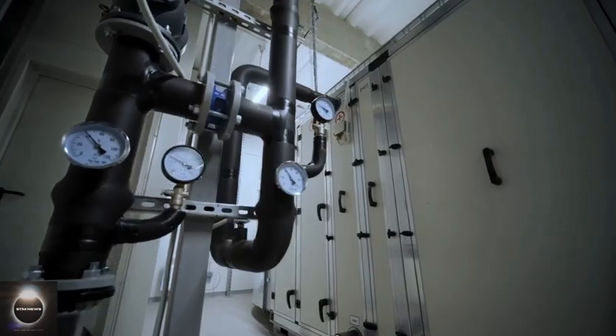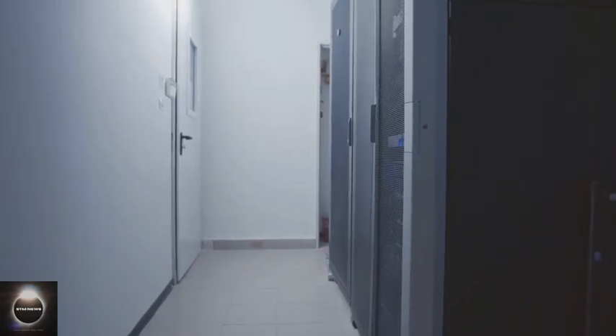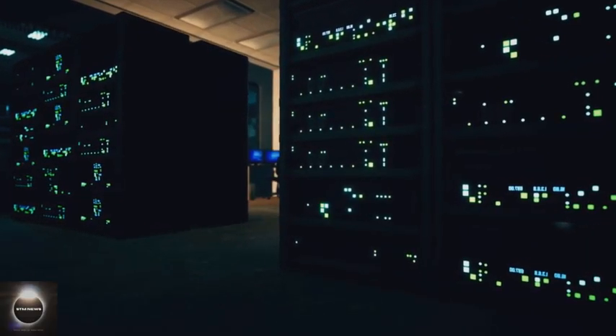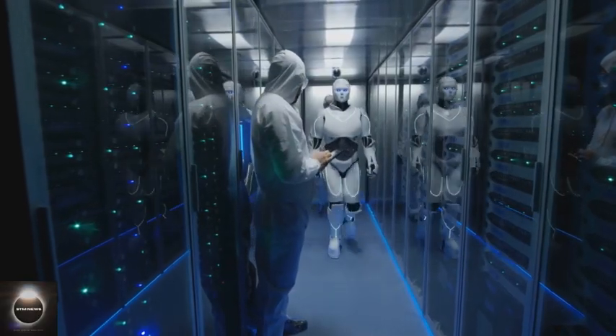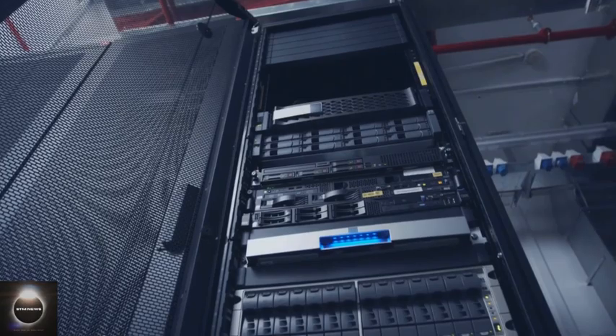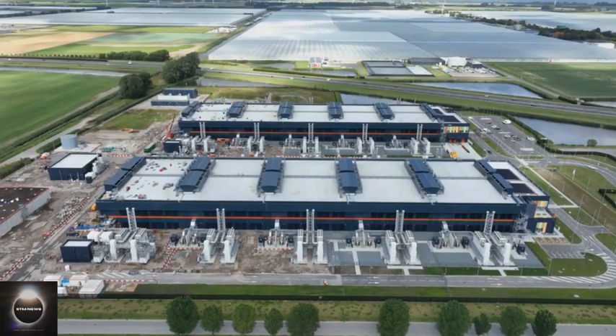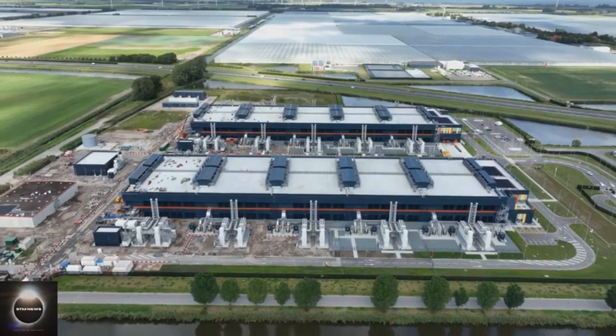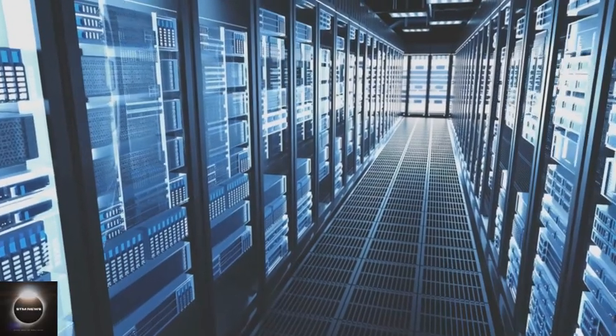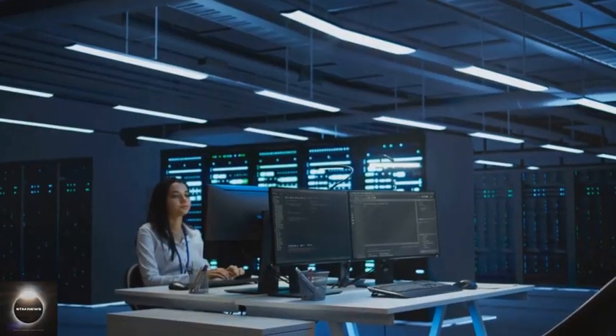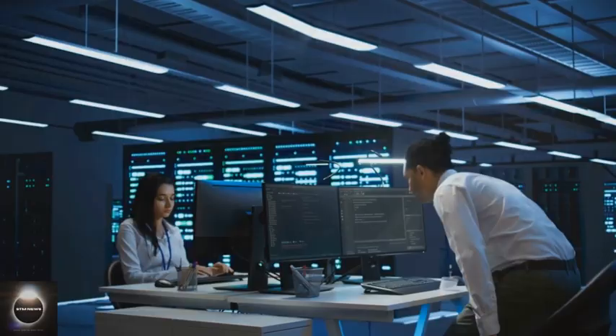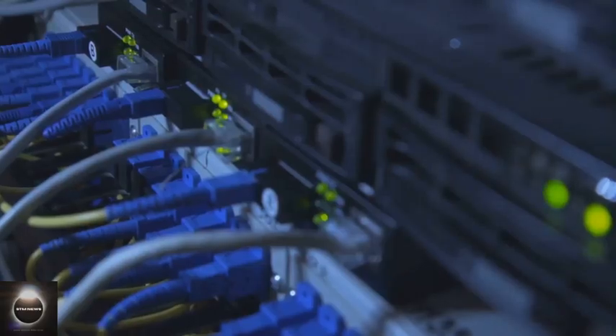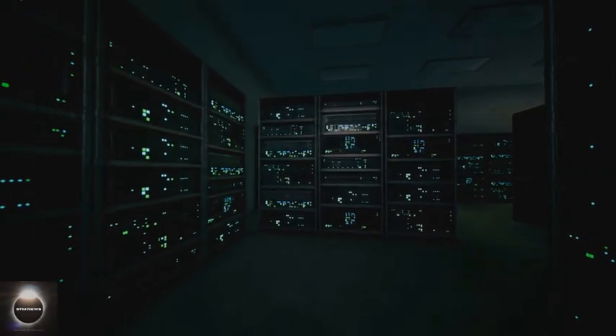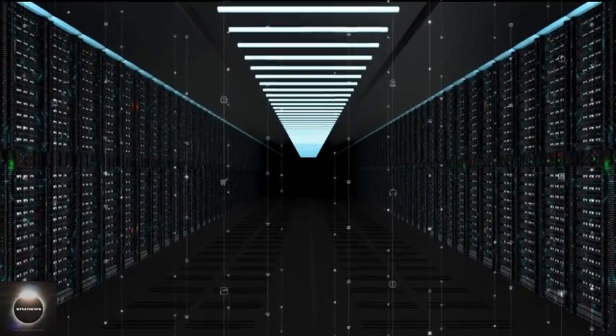The hurricane inside. All the electricity creates an incredible amount of heat. The servers, packed by thousands into racks, convert nearly all the power they draw into thermal energy. That's heat. Without some way to get rid of that heat, the entire place would quickly overheat and shut down. This is why data centers are such monumental cooling machines. A common strategy is the hot aisle/cold aisle layout. Chilled air is pumped under a raised floor and pushed into cold aisles where it is sucked through the front of servers. The servers then blast hot air into the hot aisles, where it is captured and sent back to the massive cooling units to be chilled all over again.